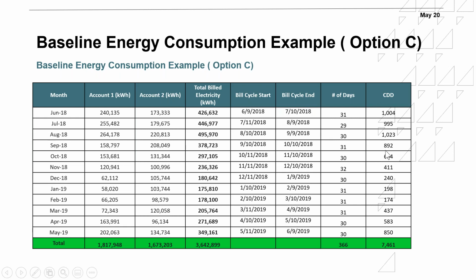I can use websites like coolingdegreedays.net to get the cooling degree days. Or if I have a weather station on site which is accurate and calibrated, I can use that to derive the cooling degree days for the specific site. Normally, I would use weather stations like Dubai Airport or similar. So here, as we can see, there's a total of around 7,461 cooling degree days with the base temperature of 65, so this is in Fahrenheit, basically. Full year, 366 days. And then this is the consumption of the building.